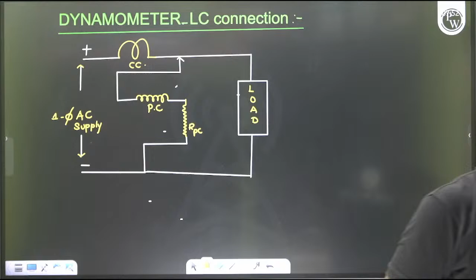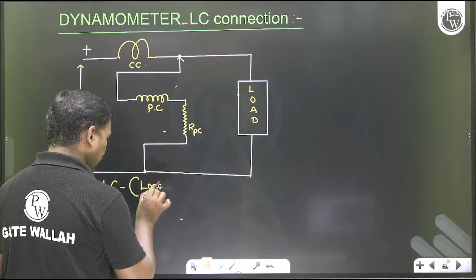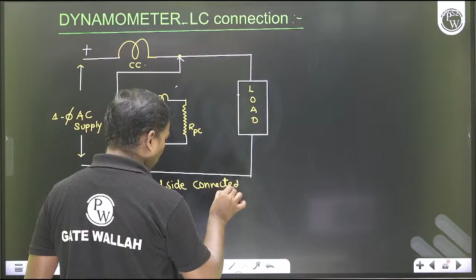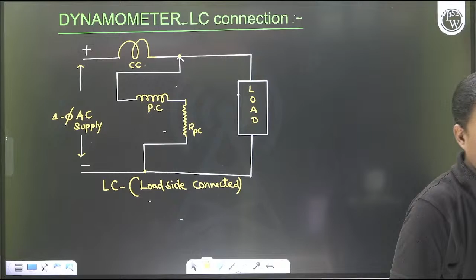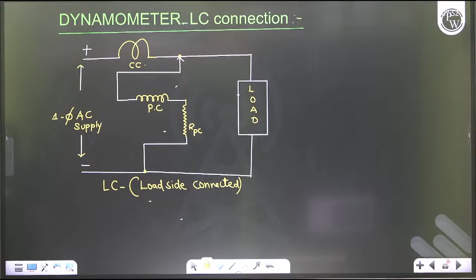Understood? Yeah, if this is a scenario, how to do? So this is the LC connection. LC means load side connected. Load side connected. Who is connected? The pressure coil. So based upon the pressure coil connection only, there will be error. If the pressure coil is connected at the main side, it is called MC connection. If the pressure coil is connected at the load side, it is called LC connection.